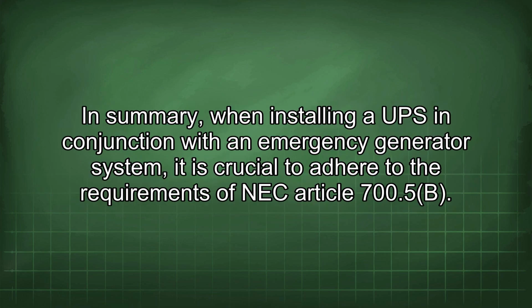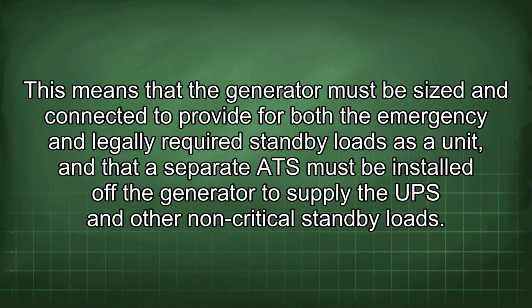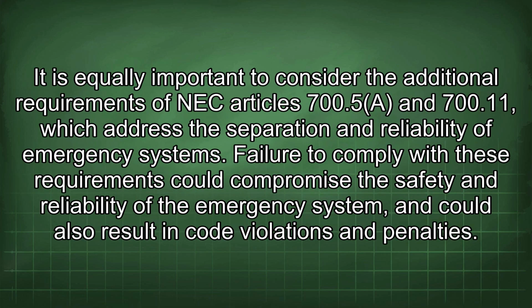In summary, when installing a UPS in conjunction with an emergency generator system, it is crucial to adhere to the requirements of NEC Article 700.5(b). This means that the generator must be sized and connected to provide for both the emergency and legally required standby loads as a unit, and that a separate ATS must be installed off the generator to supply the UPS and other non-critical standby loads. It is equally important to consider the additional requirements of NEC Articles 700.5 and 700.11, which address the separation and reliability of emergency systems.